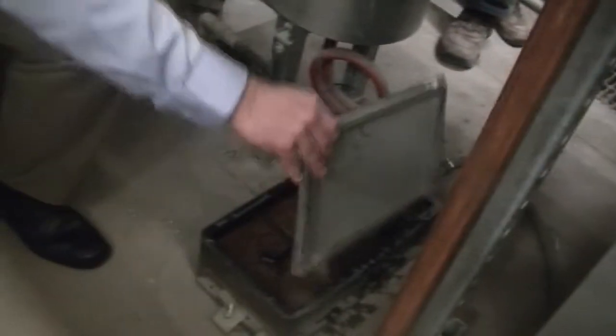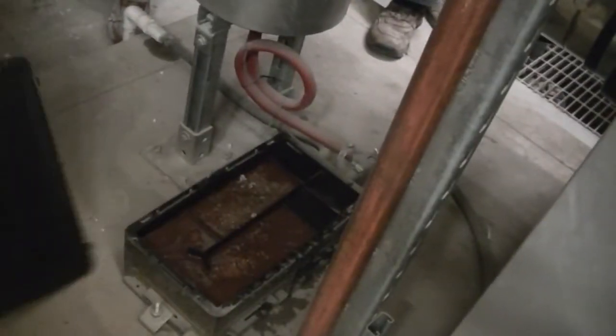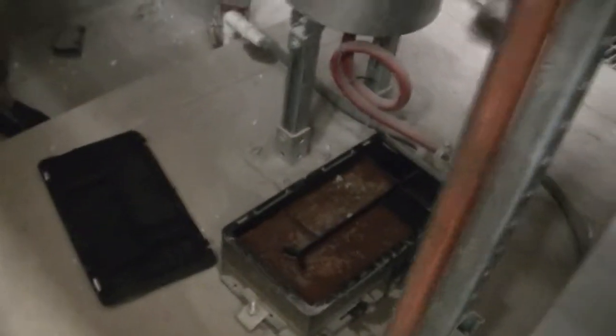So it's not magic inside. What you have inside is a box full of lime pellets, a bunch of little rocks made out of lime, to fill up that condensate neutralizer. So they don't, as we say, go bad, they just go away. After a while, those lime pellets will begin to dissolve.